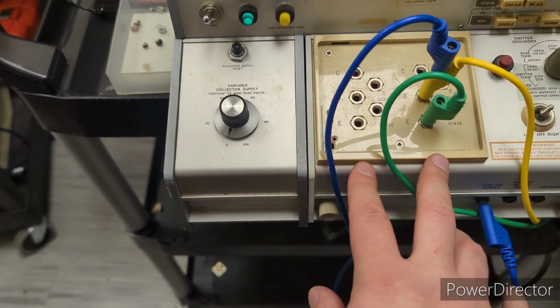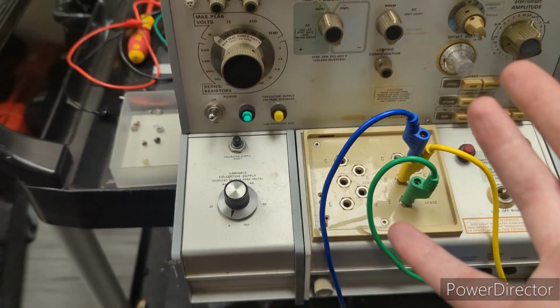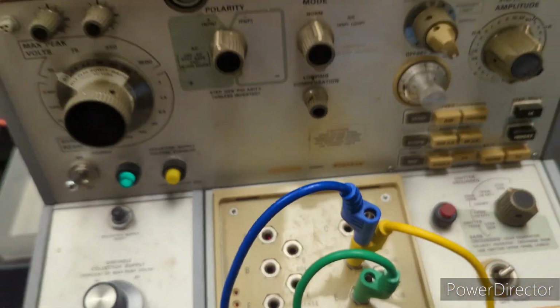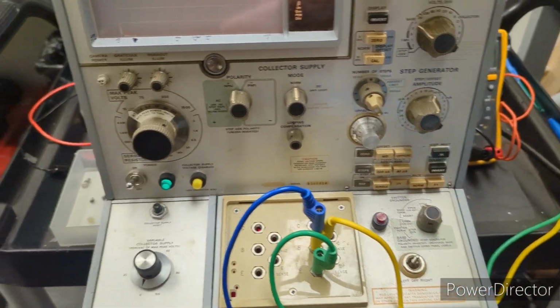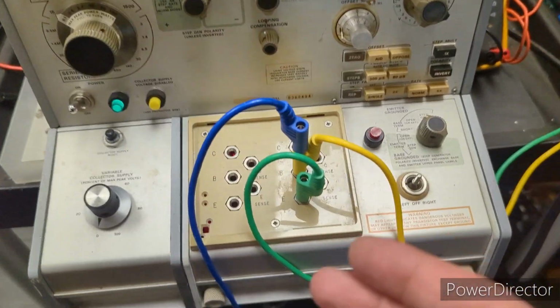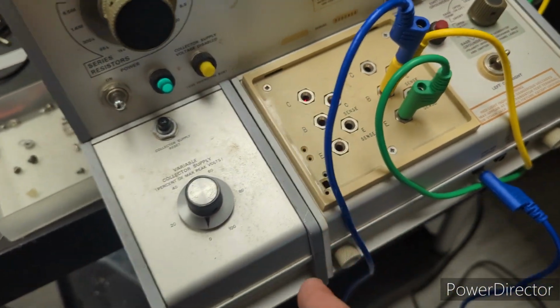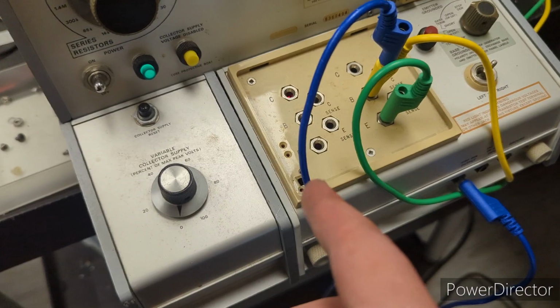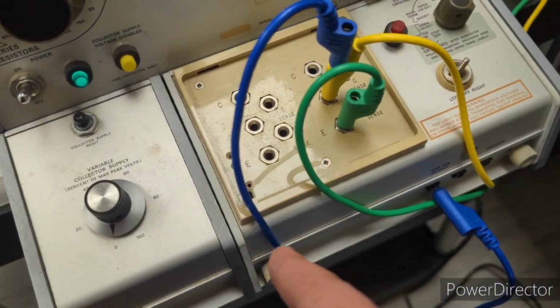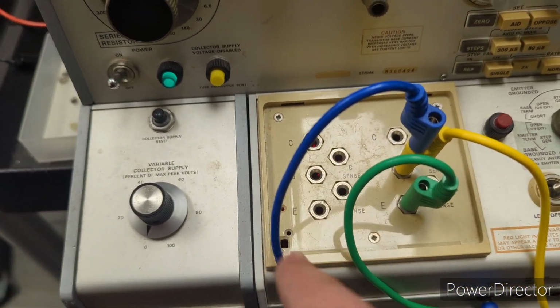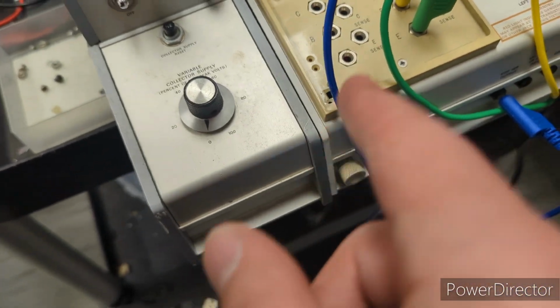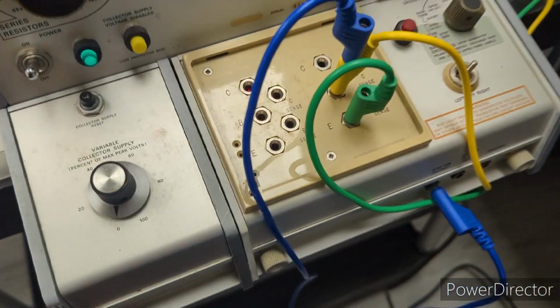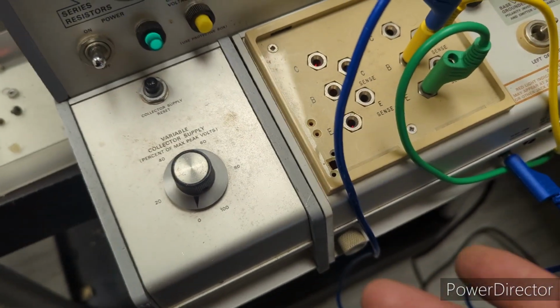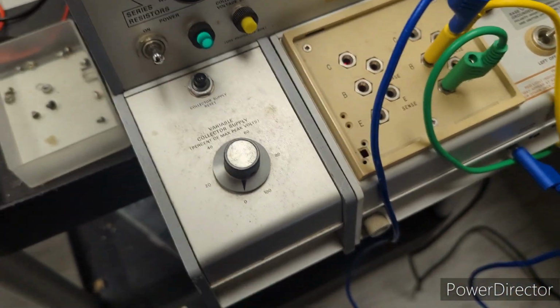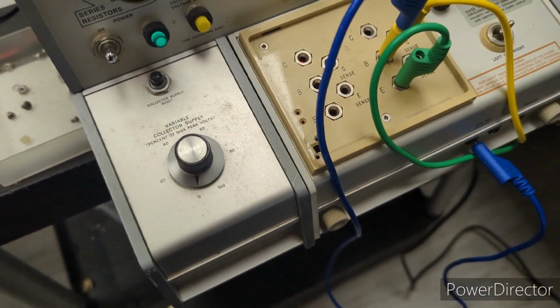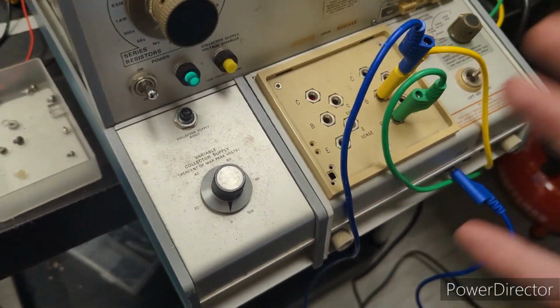This again is an instrument that, at least it has to be from the mid 80s based on its serial number, and some of the ICs have a date code from the mid 80s. So its high voltage interlock utilizes a photo micro sensor. I don't know if the older ones used that type of sensor, but that's what this one did. So I disabled it, and if you want to know what I did to do that, that's in video number 1.